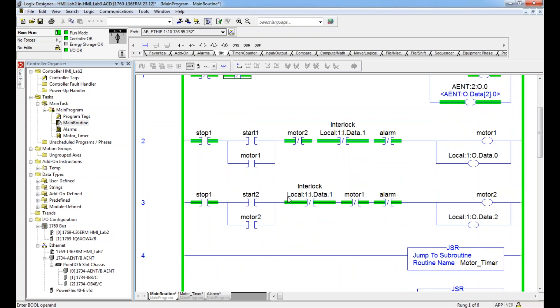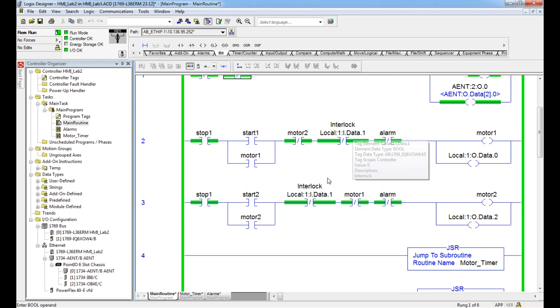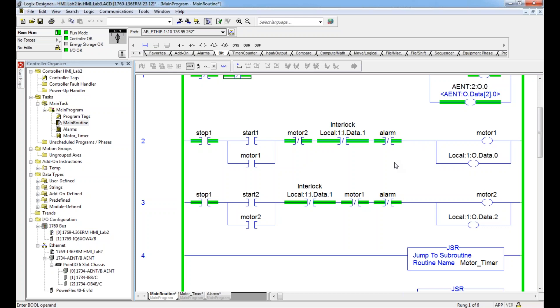I have a basic seal in with a stop and a double interlock setup so that when one motor is running, the other one can't start on, plus an actual mechanical interlock - say like the thermal overload or something like that. That's an exterior interlock that will keep the motor from kicking on when some trouble condition takes place. Maybe it's a torque sensor or something like that. And then of course an alarm bit so that when an alarm kicks on, it's going to keep these from running until the alarm has been cleared.